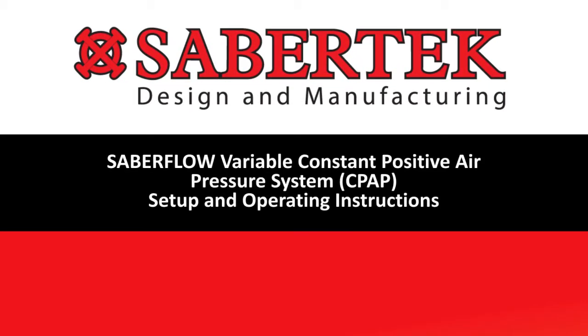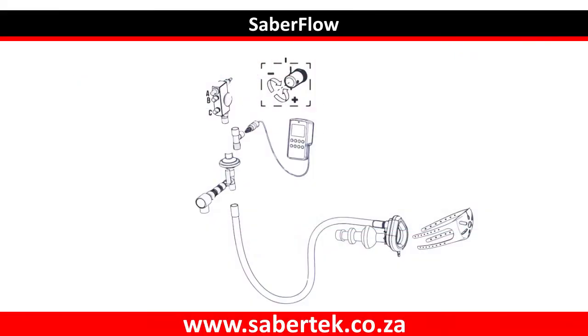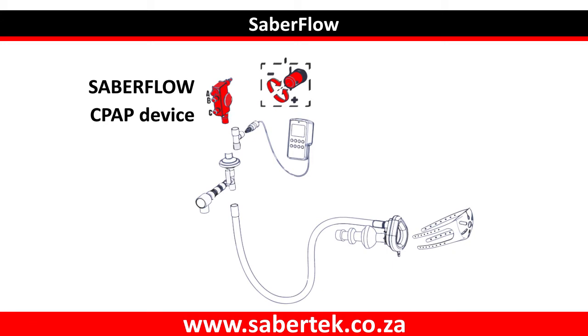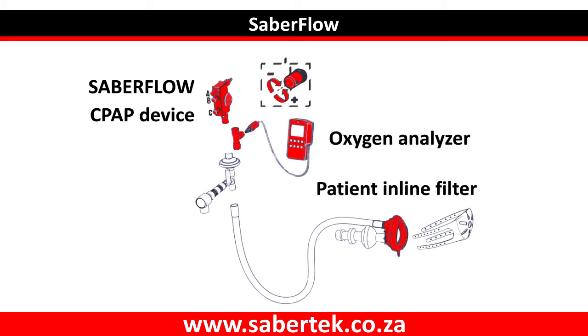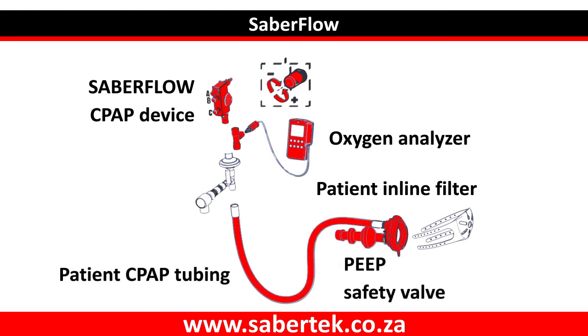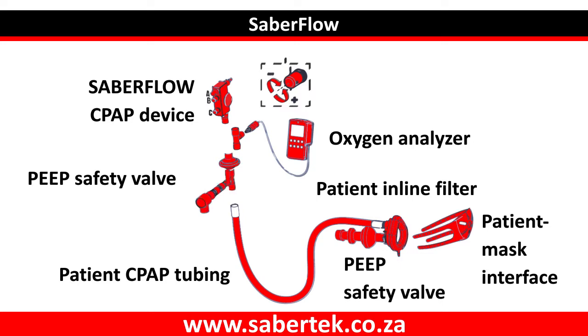SaberFlow Variable Constant Positive Air Pressure System CPAP Setup and Operating Instructions. A typical SaberFlow CPAP system is shown in the diagram. The system consists of the following main items: SaberFlow CPAP device, oxygen analyzer, patient inline filter, PEEP safety valve, patient CPAP tubing, patient mask interface, PEEP safety valve, outlet filter.